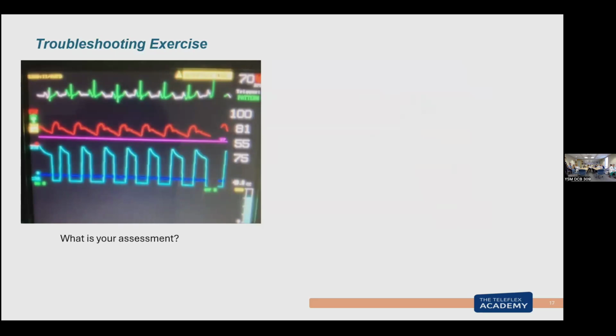Okay, if you look at this one, a couple of things you see right off. If I look at this, I am not getting back to zero between those. Now, if you look up here, I have no augmentation, because the helium can't get past whatever obstruction is there to get to the balloon, to get it inflated, to give me my augmentation. I need to figure out where this kink is pretty quick, because I'm not getting any inflation to that balloon to give you any augmentation pressure.